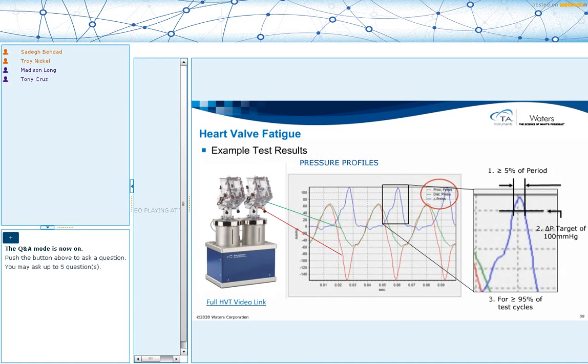So here is the instrument that we have. We call it a heart valve tester, to measure heart valve fatigue. You can have it with 2, 4, or 6 independent chambers, depending on the number of heart valves that you want to test at a time. It gives you a plot like this, which is basically what we discussed, just instrument results. Green and red show you the pressure in the distal and proximal chambers, which are representative of your aortic and ventricular pressure. And blue is just the differential of the two, right? Blue is what the standard is concerned about.